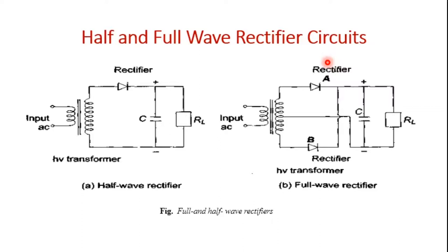The rectifier may be an electron tube or solid state device. Nowadays single electron tubes are available for peak inverse voltages up to 250 kV. Semiconductor or solid state diodes are available up to 20 kV; for higher voltages, several units are used in series. When multiple units are used in series, transient voltage distribution along each unit becomes non-uniform, and special care must be taken to make the distribution uniform.